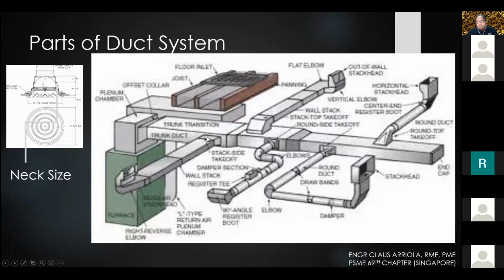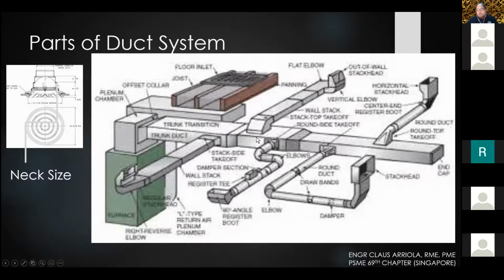So, for example, we have a trunk duct, then we have these branch ducts, we have round duct, and we have terminals, okay? So, in engineered smoke control, you can design rectangular and you can design circular duct. Depends on your architectural layout, which is more advisable. If it's a large space, you can design circular duct. If it's just a normal space, rectangular duct to save space for other services can be considered.